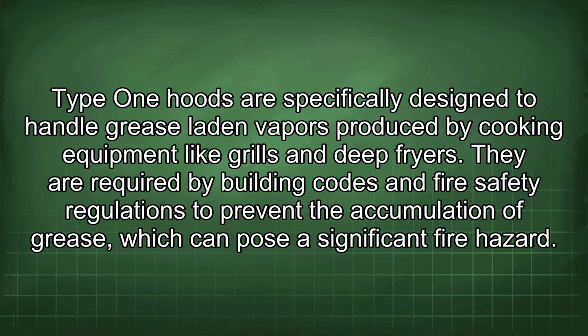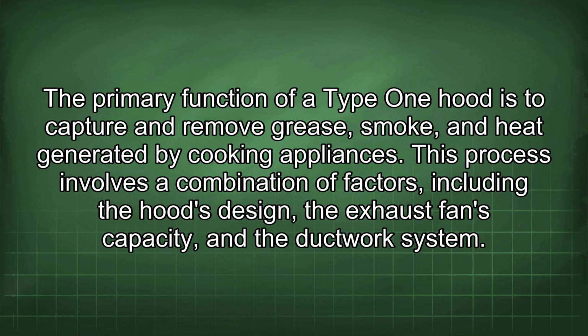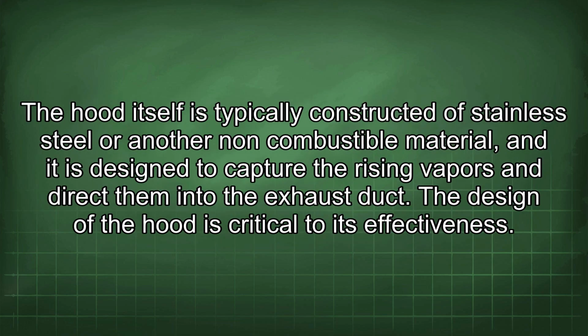They are required by building codes and fire safety regulations to prevent the accumulation of grease, which can pose a significant fire hazard. The primary function of a Type 1 hood is to capture and remove grease, smoke, and heat generated by cooking appliances. This process involves a combination of factors, including the hood's design, the exhaust fan's capacity, and the ductwork system. The hood itself is typically constructed of stainless steel or another non-combustible material, and it is designed to capture the rising vapors and direct them into the exhaust duct.